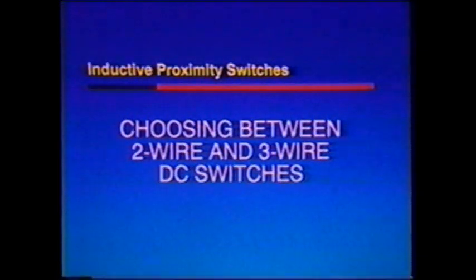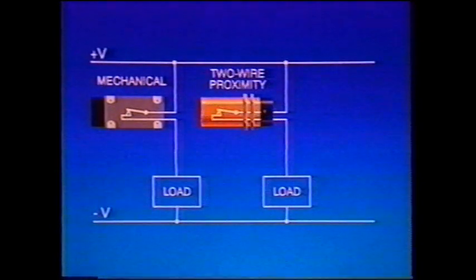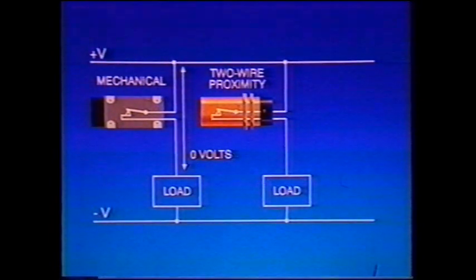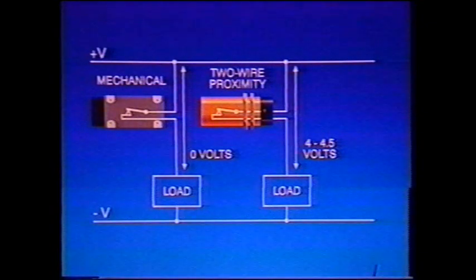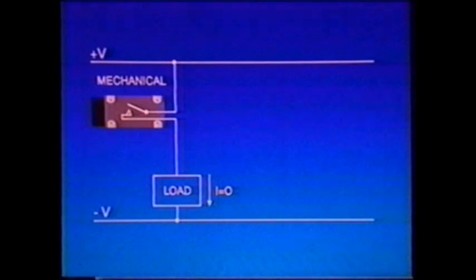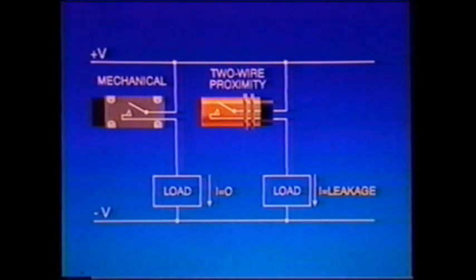There are two types of DC switches: two-wire DC switches and three-wire. AC and AC-DC switches are two-wire devices. With DC switches, you have a choice between two-wire and three-wire units. The familiar mechanical switch has two wires and is simply wired in series with the load, and a two-wire proximity switch is wired exactly the same way. When the mechanical switch is closed, it has essentially a zero voltage drop, but the proximity switch has a voltage drop in the order of four to four and a half volts. When a two-wire switch is open, there is a small current called leakage current flowing through the circuit.